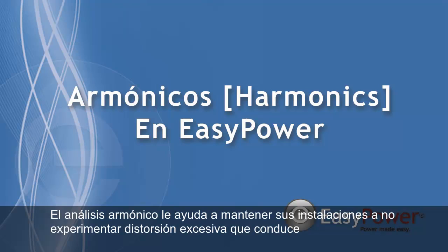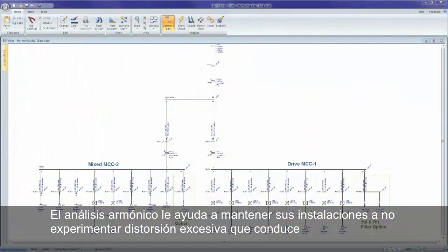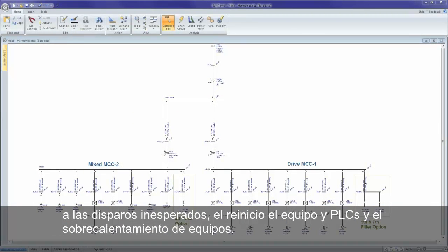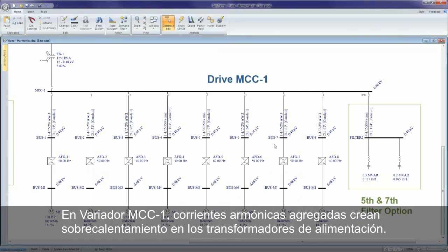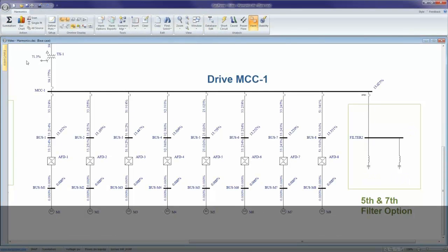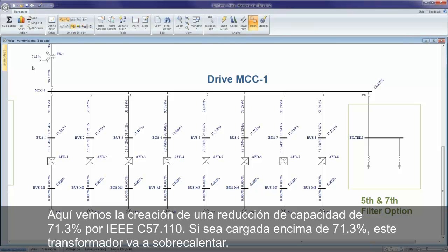Harmonic Analysis helps you keep your facility from experiencing excessive distortion that leads to unexplained false trips, computer and PLC reboots, and equipment heating. At drive MCC1, accumulated drive harmonic currents create overheating in supply transformers. Here we see a 71.3% IEEE C57-110 derated capacity created. If loaded over 71.3%, this transformer will overheat.